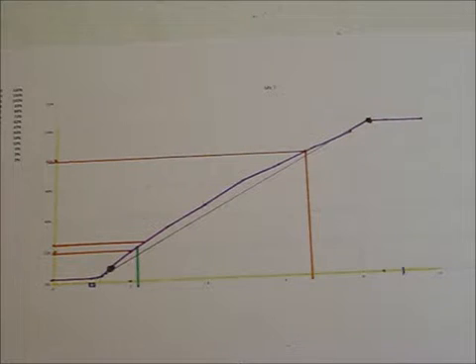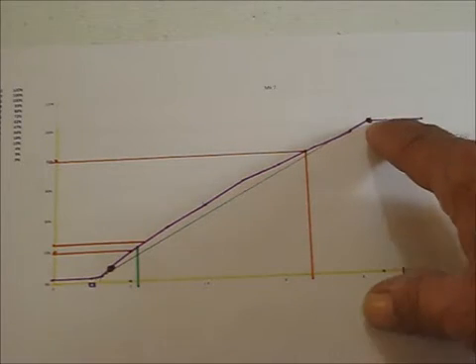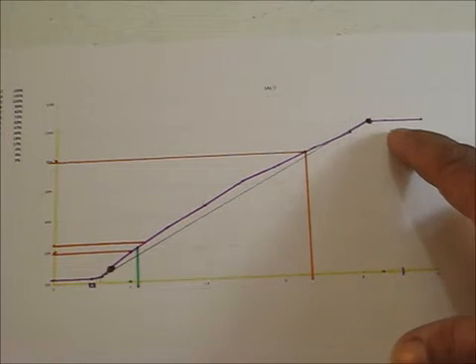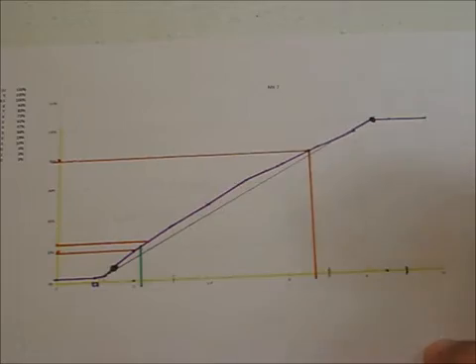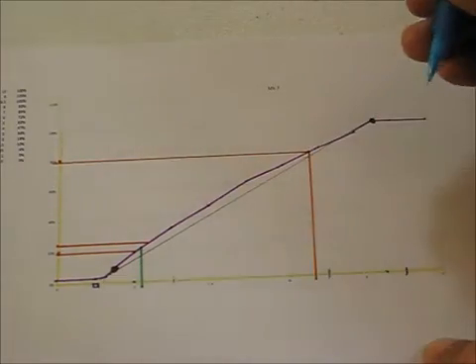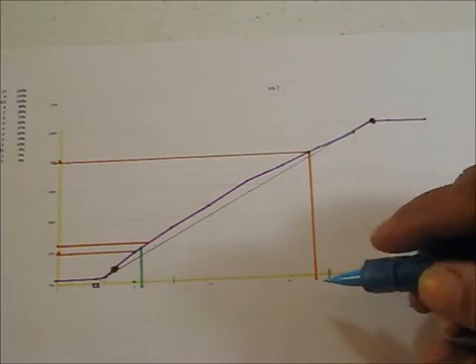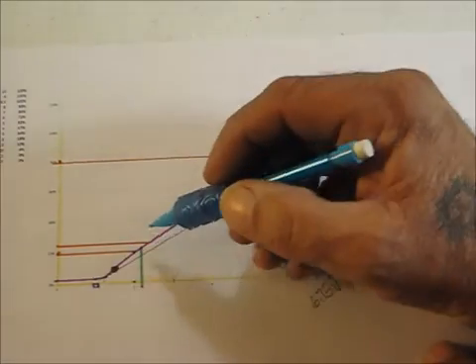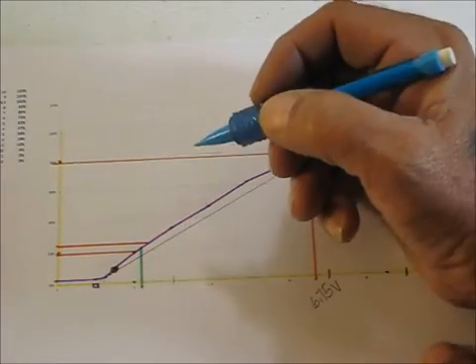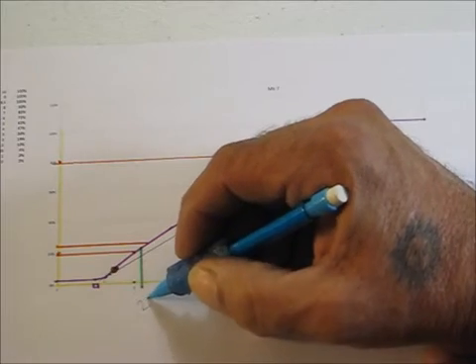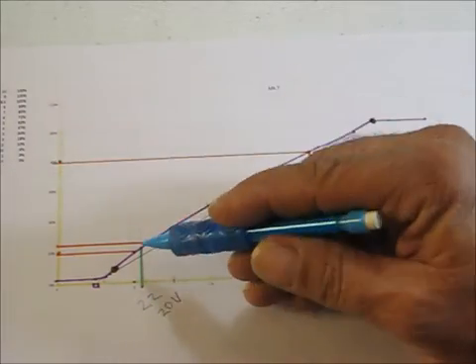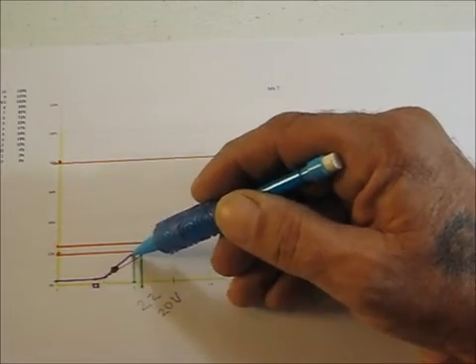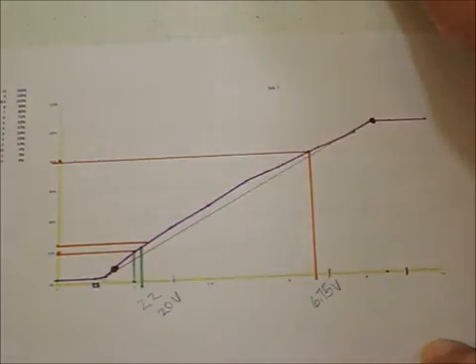So, that is the response curve approximately for a Mark 7, 0 to 10 volt advance Philips dimming ballast. So, we have for about an 80% demand response level, a voltage of somewhere around 6.75 volts and for bottom end of daylighting somewhere between 2.2 and 2 volts to ensure that you have driven the lighting down to get your 75 to 80% illumination reduction.